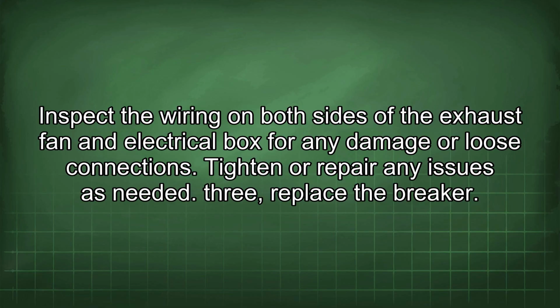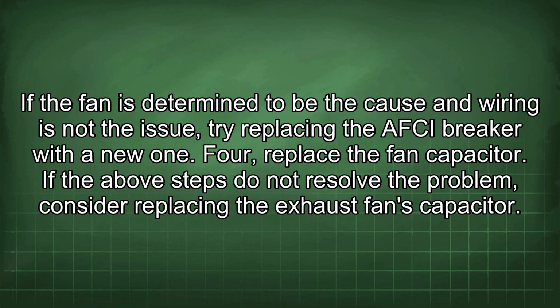3. Replace the breaker. If the fan is determined to be the cause and wiring is not the issue, try replacing the AFCI breaker with a new one. 4. Replace the fan capacitor. If the above steps do not resolve the problem, consider replacing the exhaust fan's capacitor.